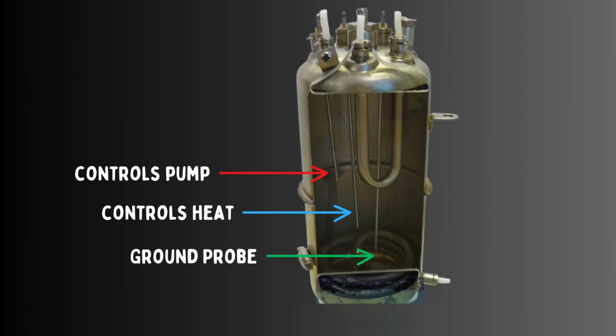Okay, a few things can go wrong during a descale, and these usually occur just before the rinse stage when the boiler's empty. Number 1, the boiler stays cold and empty. Here, the red probe thinks it already has water in, so it doesn't tell the pump to turn on. Because the blue probe's working okay, that means the heat doesn't come on either. This is the best case scenario, as although the steam won't work, nothing is actually physically damaged. And you can usually fix this by cleaning up the red probe and turning it on again.